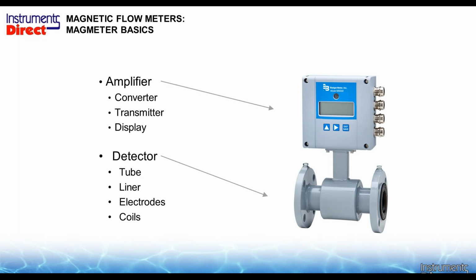So to break this guy down, there's two parts basically to a mag meter. And sitting on the top of this mag meter here, this is either called an amplifier, or I call it a transmitter indicator display, or the converter. So this device is your electronics basically here that will receive the signal, process the signal, give you some information. And down here, this is the flow tube. And this flow tube would be made up of, depending on the design, this design has flanges here, and then we have a liner. You can see the end part of the liner right here. And then inside that liner will be the two electrodes. And in this big metal can here, there are copper wires wrapped around the pipe here, so to speak.